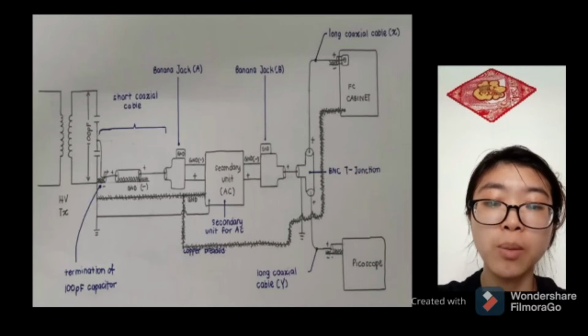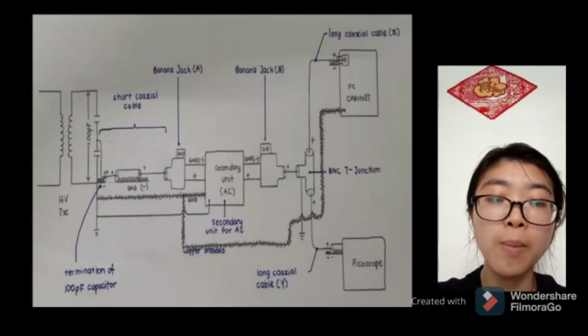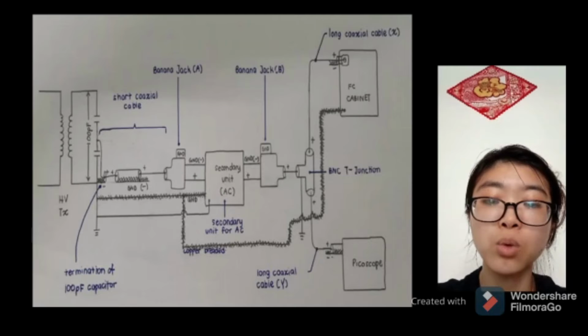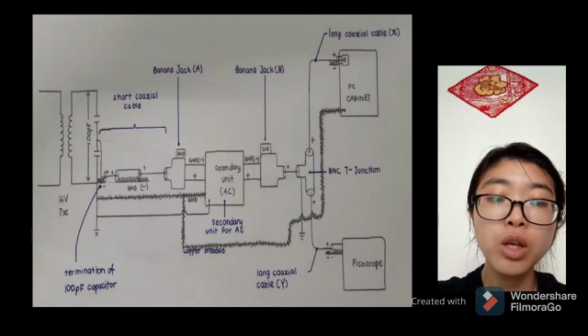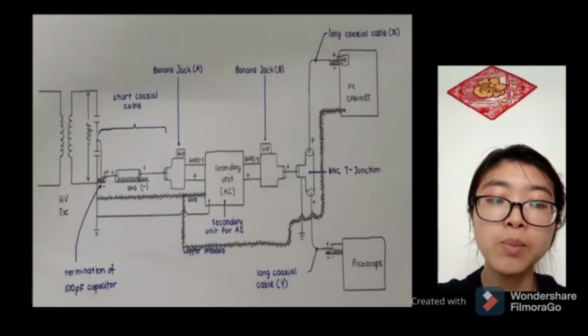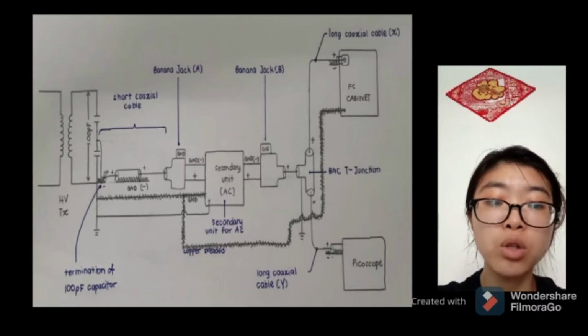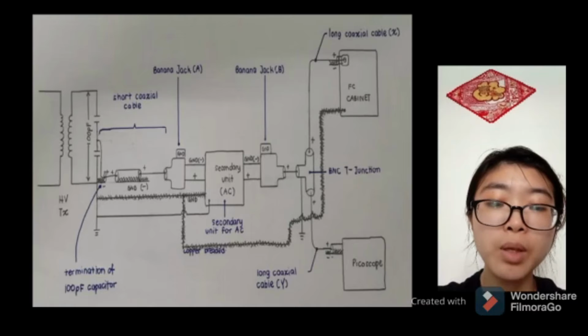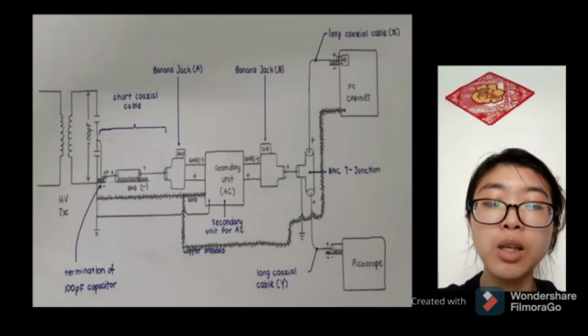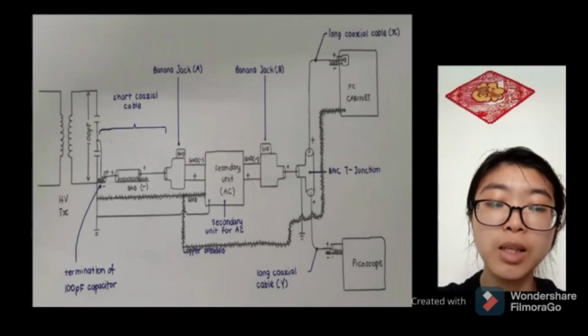After the connection is complete, remember to double check by making a little pulling test to ensure that the connections have been plugged in properly. GND is the grounding. It must be ensured that the earth part is connected to the body of the enclosure, which is connected to the grounding cable. Remember to ensure that the earthing switch has touched the capacitor properly. The connection cables must be kept clean by placing them neatly.